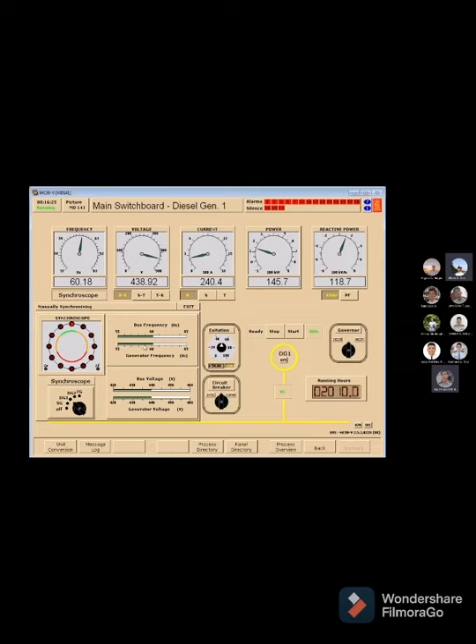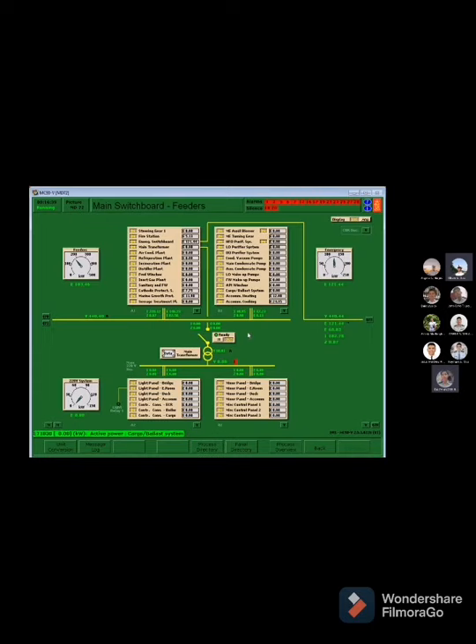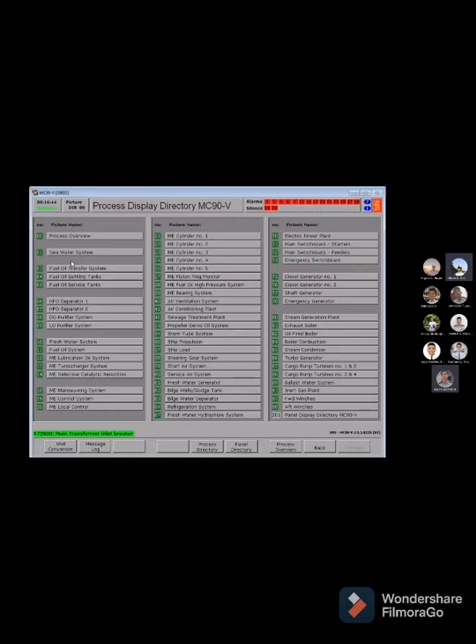Go to MD01 and start the auxiliary pump again. Next. Go to MD72, main switchboard feeders, main transformer inlet breaker, in. Go to MD01 and start main seawater pump number 1, then put it to remote. Okay, done.